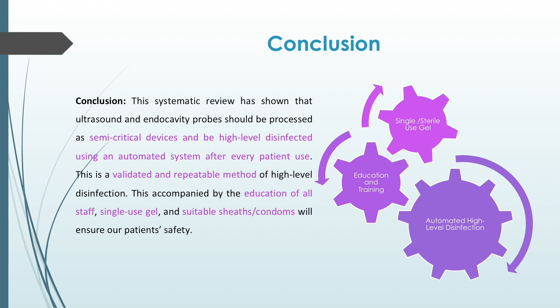Disinfection of the ultrasound probe after each patient is essential. Standardisation, more user-friendly guidelines, and standard operating procedures for all staff is vital. More research is required into the use of sterile gel and probe covers. And when all of these factors are taken into consideration, it will help us reduce the transmission risk of healthcare-associated infections to our patients. This systematic review has shown that ultrasound and endocavity probes should be processed as a semi-critical device and be high-level disinfected using an automated system after every patient use. This is a validated and repeatable method of high-level disinfection, and this accompanied by education of all our staff, single-use gel, and suitable sheaths/condoms will ensure our patient safety.